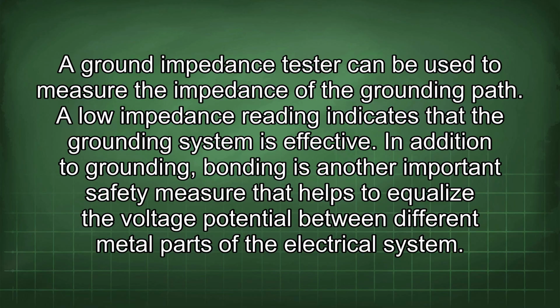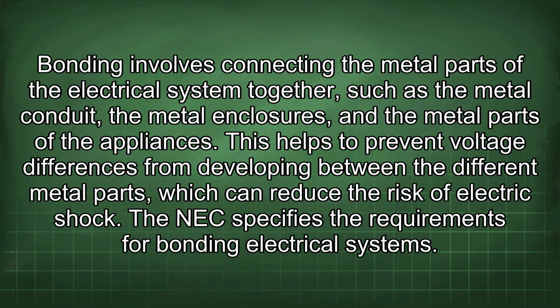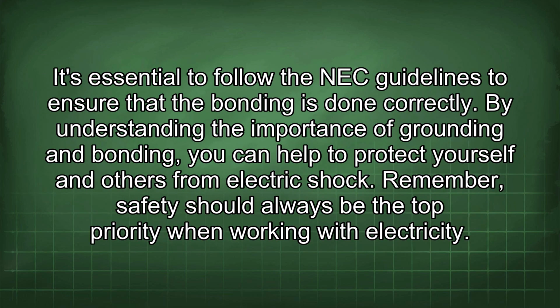In addition to grounding, bonding is another important safety measure that helps to equalize the voltage potential between different metal parts of the electrical system. Bonding involves connecting the metal parts of the electrical system together, such as the metal conduit, the metal enclosures, and the metal parts of the appliances. This helps to prevent voltage differences from developing between the different metal parts, which can reduce the risk of electric shock. The NEC specifies the requirements for bonding electrical systems. It's essential to follow the NEC guidelines to ensure that the bonding is done correctly.